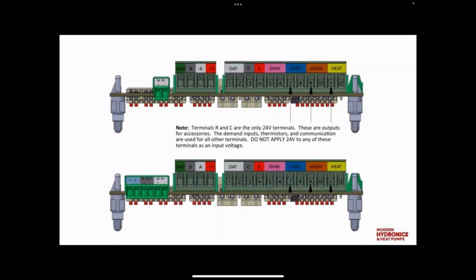And so, in order for the backup to come on, whether we're talking electric or a dual fuel system, the compressor would have to be at 100% capacity, and we're still not reaching our target temperature. There's also a time component in there, which is adjustable by the user, and that timer would have to expire in that mode.